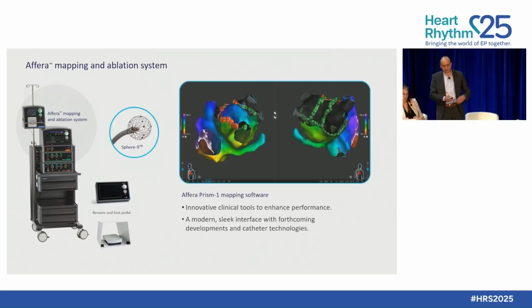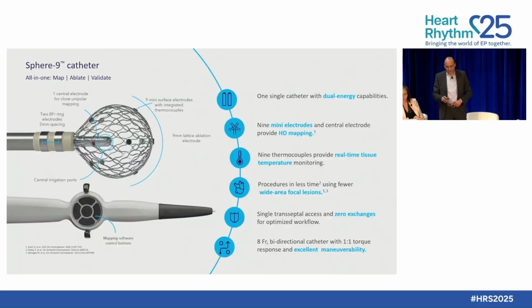You see them on the left side of the screen. And then you have the catheter itself, which is a 9mm sphere. It's self-expanding. It has 9 electrodes in it. And what you see on the right side is a couple of maps obtained with this catheter. And here's a close-up view of the Sphere-9 catheter. It has one central electrode for close unipolar mapping. It has 9 mini surface electrodes with integrated thermocouples and a 9mm lattice ablation electrode.